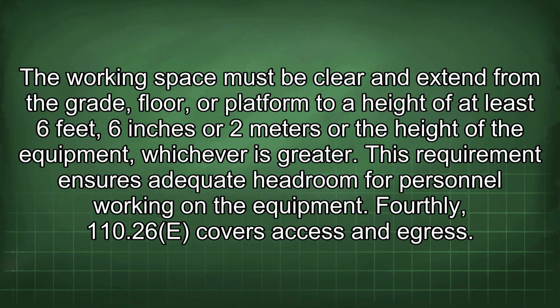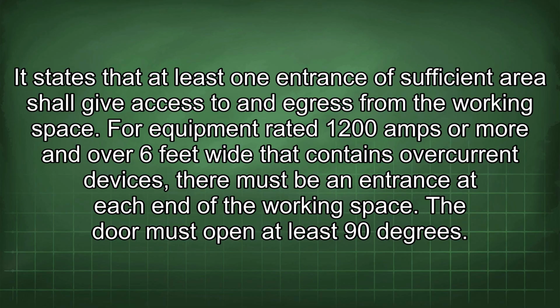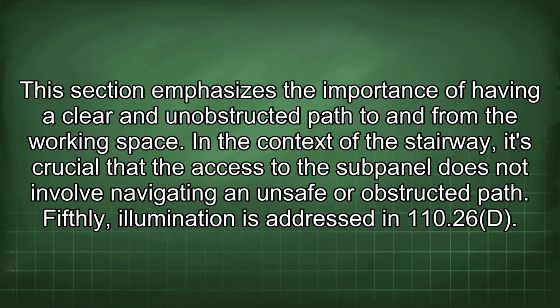Fourthly, 110.26e covers access and egress. It states that at least one entrance of sufficient area shall give access to and egress from the working space. For equipment rated 1200 amps or more and over 6 feet wide that contains overcurrent devices, there must be an entrance at each end of the working space. The door must open at least 90 degrees. This section emphasizes the importance of having a clear and unobstructed path to and from the working space. In the context of the stairway, it's crucial that the access to the subpanel does not involve navigating an unsafe or obstructed path.